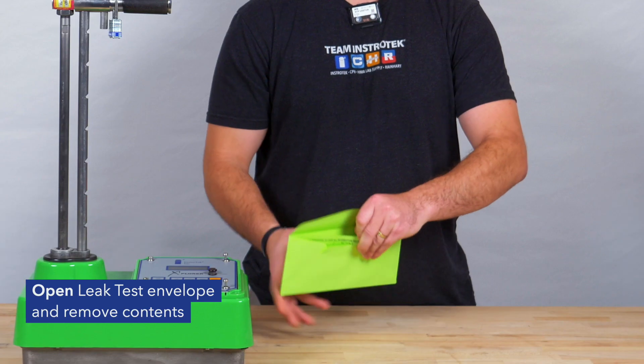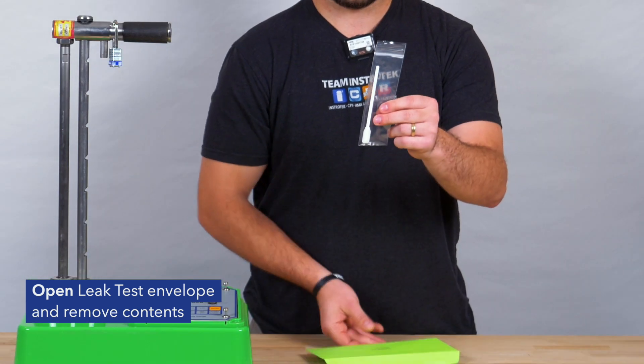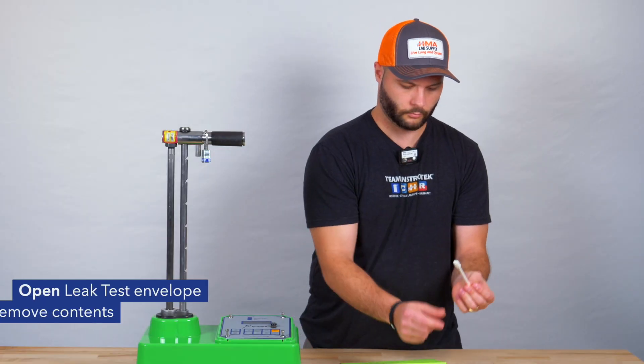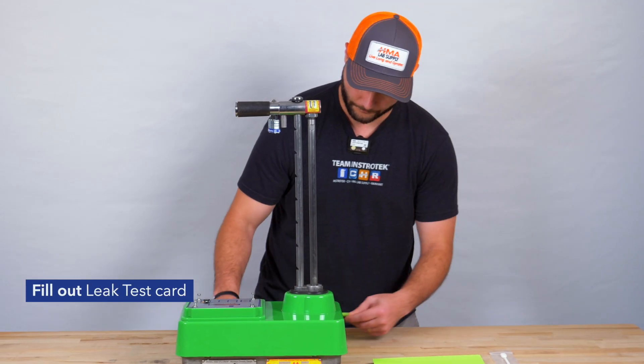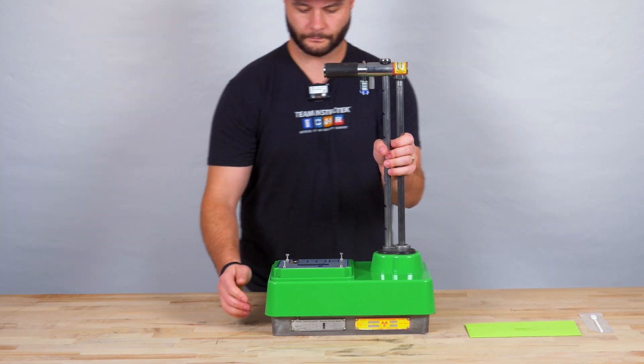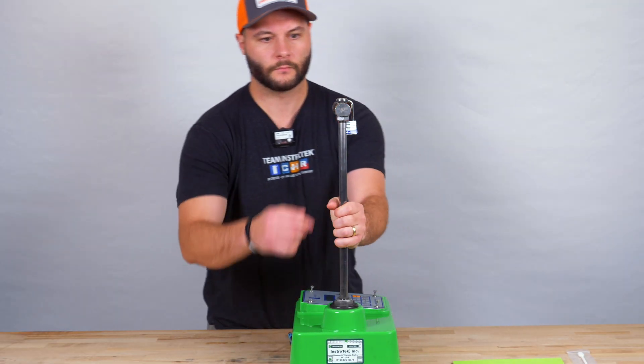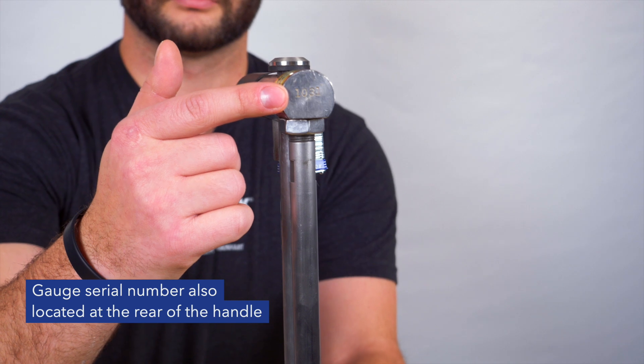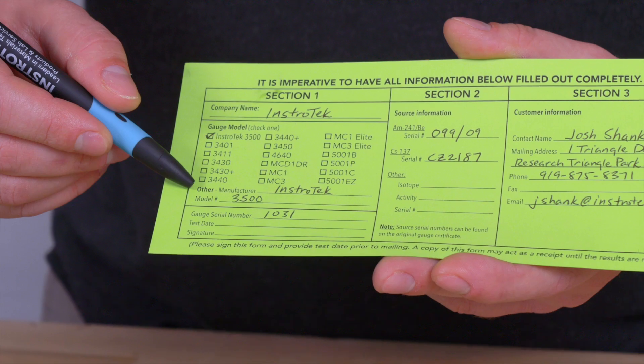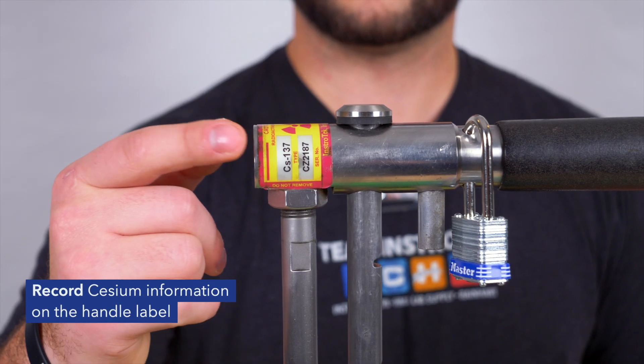Open the leak test envelope and remove contents. Fill out the leak test card. Record the model and serial number located at the base of the gauge. The gauge serial number is also located at the rear of the handle. Record Cesium information on the handle label.